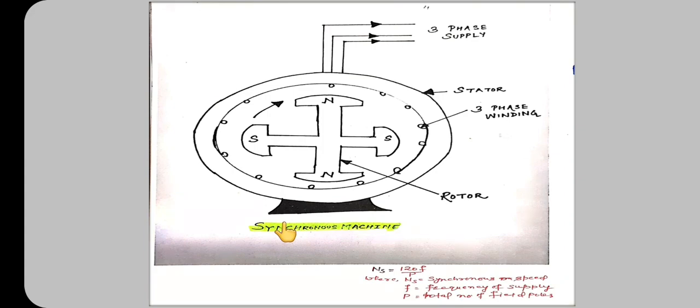Due to simple, light and robust construction of the rotor, higher speed of the rotating DC field is possible. This results in increased output from a machine of given dimensions. So, for all these reasons, all alternators above 5 kVA employ a stationary armature and revolving field.